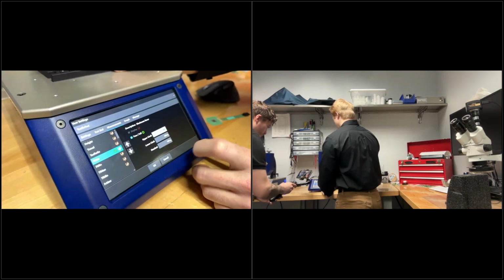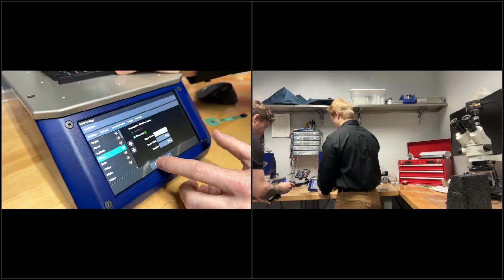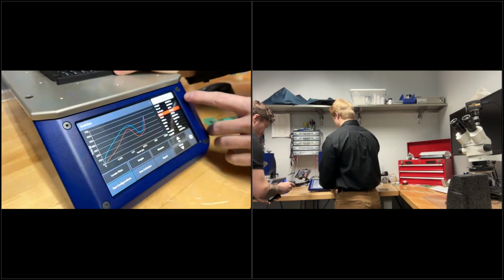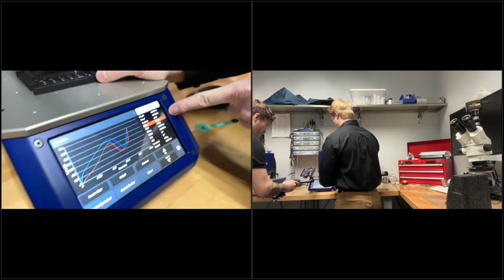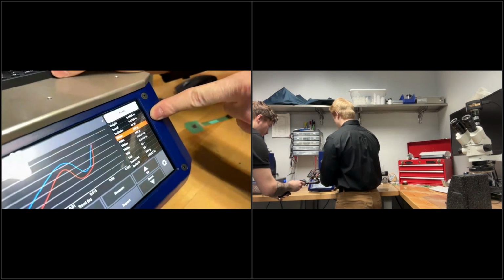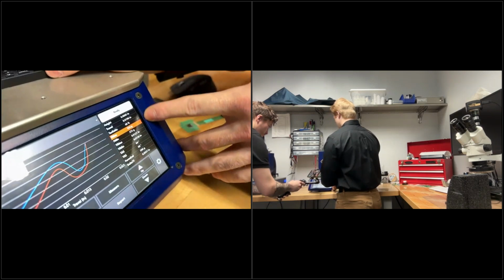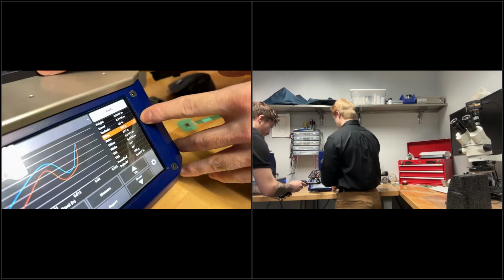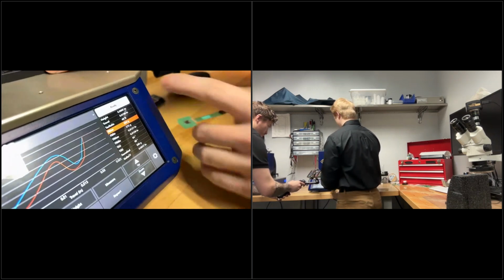So what this means is that if any of these dome switches or positions test between 200 and 400 grams, it'll be a pass according to the machine, and it will show you right here if it passes or fails. This last one tested at 500 grams, and it highlights that characteristic as red as it has been over that upper threshold.